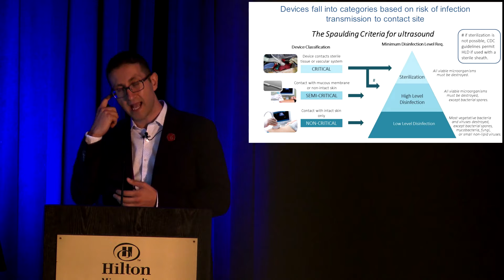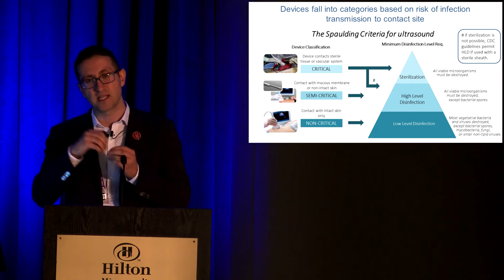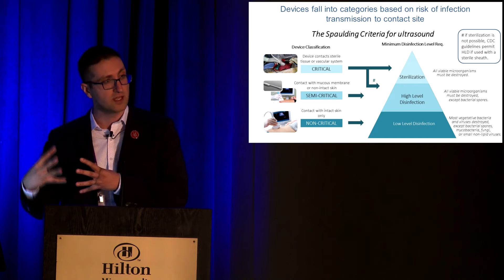Now, CDC has addressed this in the past, in which they do call out that if sterilization cannot be achieved, high-level disinfection is appropriate as long as it is used with a sterile sheath.